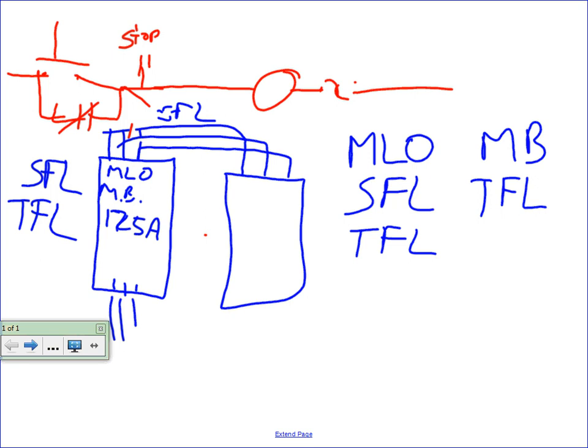We do offer, and again, I'm giving you my card, so if you guys have questions and want to know what type of panel would be best to use, call me. But on these NF and Q type panels, we do also offer what we call a sub-feed breaker. We have our interior in here that all the branch breakers plug onto. At that point, we put those feed-through lugs I was talking about in there, but then we actually mount a breaker separately in that enclosure and then cable it to those feed-throughs, and that can go up to like a 250 amp breaker.